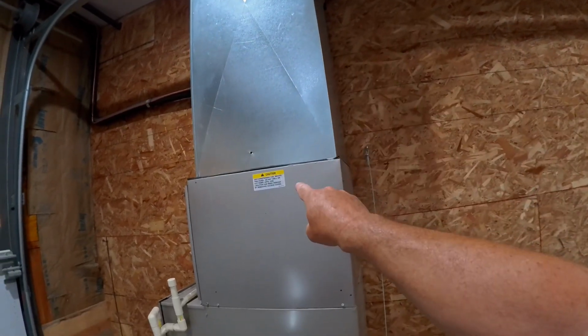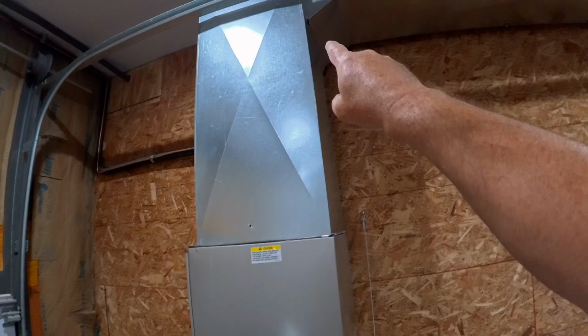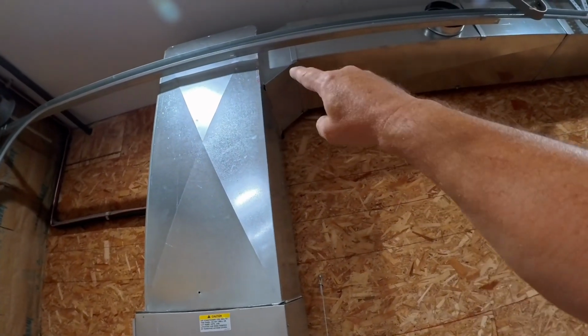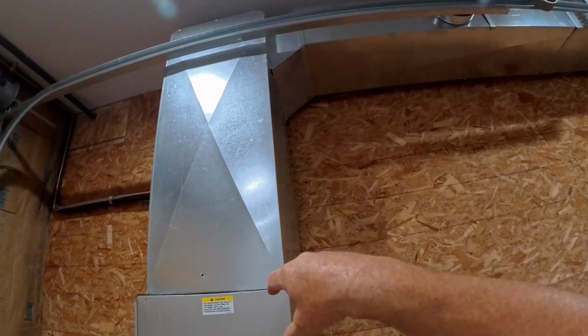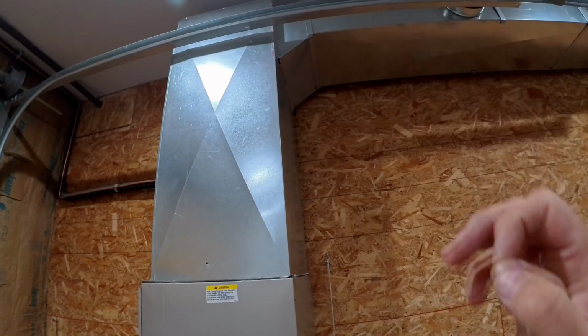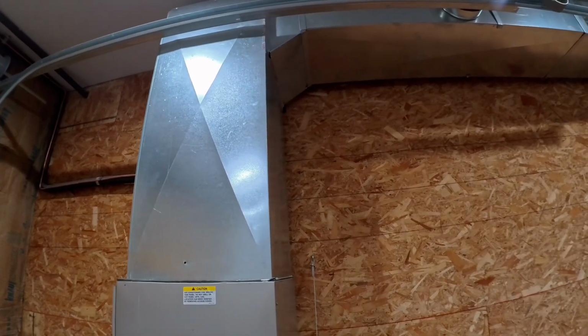We're not going to do it right above the A coil. I like to go up to the first takeoff where the ductwork connects to the plenum. And by going up about 4 foot, you're going to get an accurate measurement. So let's do that.